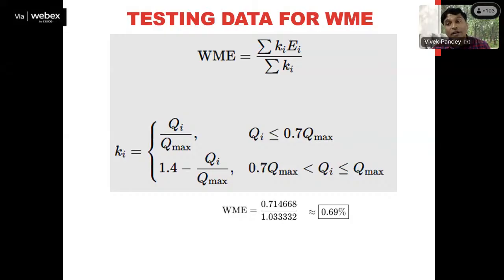But the moment our flow rate increases more than 0.7 times Qmax, in that case, what will happen? We will apply the formula Ki is equal to 1.4 minus Qi upon Qmax. So these two formulas we can use according to the flow rate to calculate K1, K2, K3, K4 and K5 for the 5 points. And what is Ei? Ei is simply E1, E2, E3, E4, E5. E means error, the error observed on the gas meter at a certain flow rate.